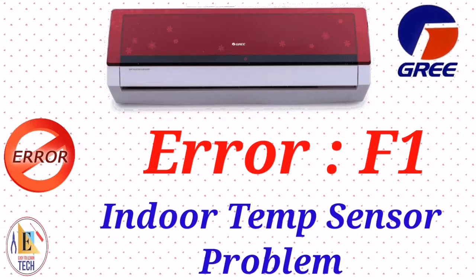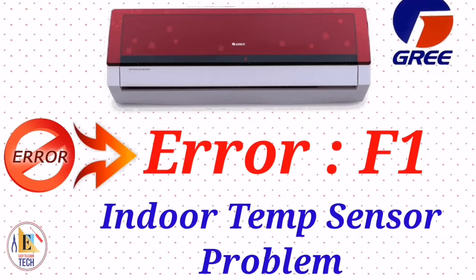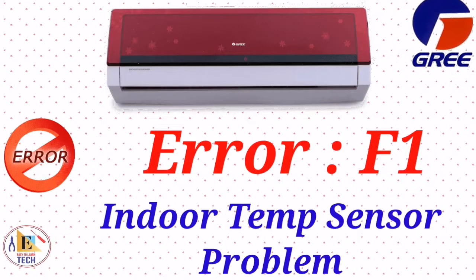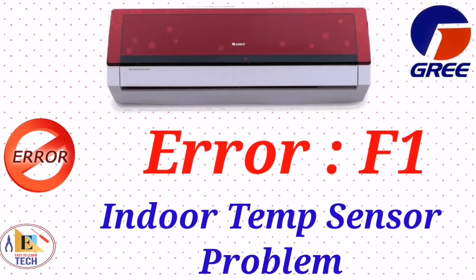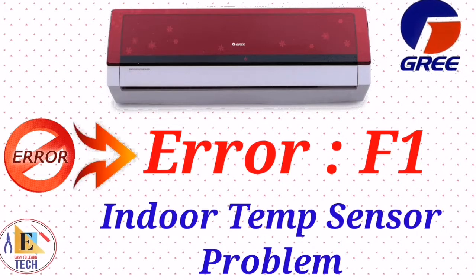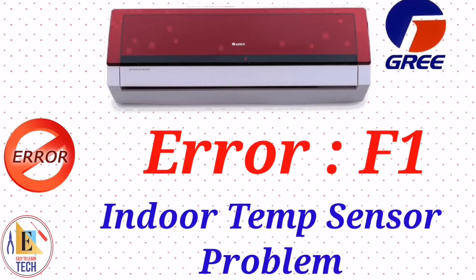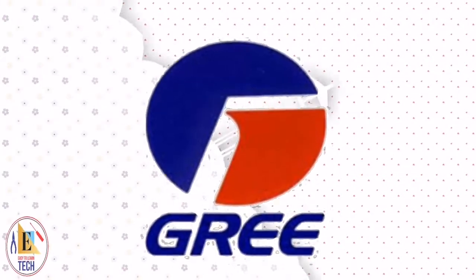If the resistance is okay, then you have to check the PCB and find out if the output for the indoor temperature sensor from the PCB is good or not. If it is not good, then you have to change the PCB. Your unit will be in working condition. Let's see the next error code.